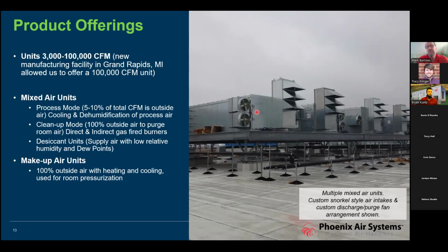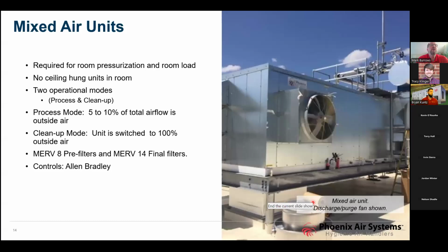So you have to be very cognizant of what the air discharge looks like both in the room and the discharge up on top of the roof as well. Yep. Mixed air units, again, these are required for pressurization. And again, they are going to replace all the ceiling hung units. There'll be no evaporators or ceiling hung units in this space. All of that load is going to be taken care of on the unit itself.